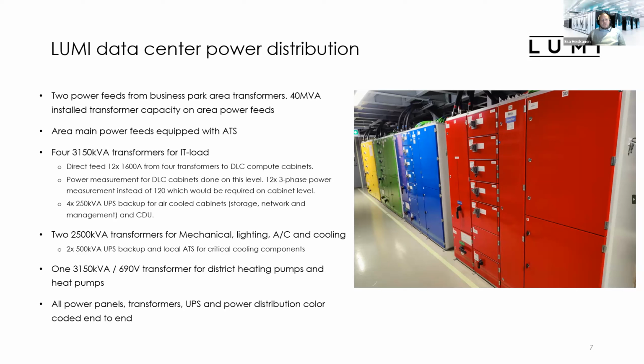Our low voltage system in Europe is 400 volts, but we have one transformer which is over 3 megawatts with 690 volts. This is only for the district heating pumps and other district heating components like heat pumps. And as you can see from the picture, we have very nicely colored power panels installed underneath the raised floor of the data center. All of our power panels, transformers, UPSs, and power distribution are color-coded end-to-end. This includes the cable labels also being color-coded. So when you are operating with electricity on the two floors, you can immediately see in case of failure where this power is fed from by the color of this power distribution.